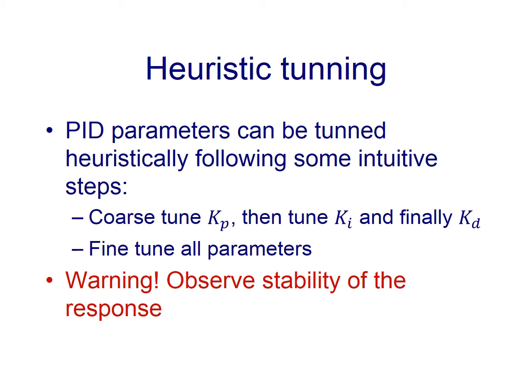So PID parameters can be tuned following some intuitive steps. First of all, let us coarse tune Kp. I mean, the order is important. Then tune integral gain, and finally we go for derivative gain. Once we have those, then we fine tune all parameters. And always, always observe stability of the response.